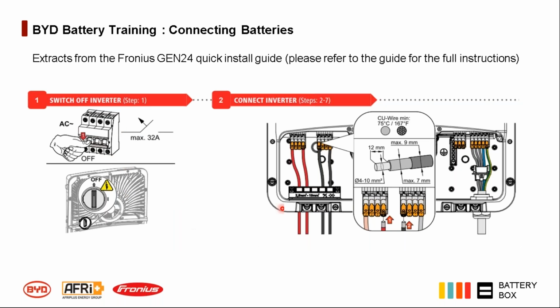Next is connecting the inverter. These are just extracts from various manuals - it's always best to refer to the installation manuals for the full guide, but this gives an idea of how to install. Here we've got the battery cables. Because it's a high voltage system, you're actually using smaller cables. For instance, on a 10 kilowatt system, your cables are only 10 millimeters squared, and there are only 2 cables. That's the other advantage of high voltage systems - smaller cables to deal with, which makes things easier to install.